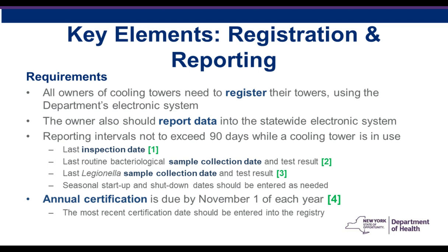Bacteriological samples should occur at intervals not to exceed 30 days, although many towers routinely sample much more frequently. The owner can report these data as they are acquired or less frequently, as long as they report at intervals not exceeding 90 days. The most recent sample collected and analyzed should be reported at the 90-day interval along with Legionella sampling, and most people do that along with their inspection dates.